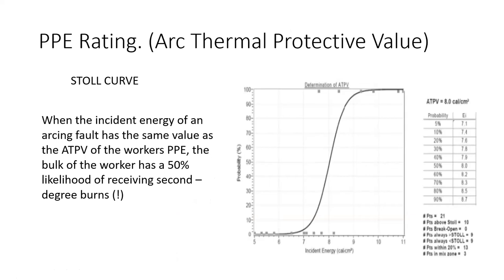This one's a real cruncher, and at first it's quite a depressing slide, because what it's saying here is, if you've got an arc flash suit that's made with a cloth with an arc thermal protective value of 8 calories per square centimeter, and the incident energy to the person wearing that happens to be 8 cals, the probability of that energy breaking through the suit is 50%. So you've only got a 50% likelihood of not receiving second degree burns, which is the same as saying you do have a 50% likelihood of actually receiving the second degree burns.